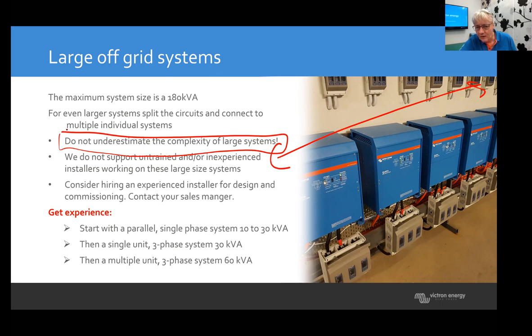Just try to calculate at 48 volts DC what the currents would be with a 180 kVA system. You need to know how to properly size cables, how to put bus bars in, what the problems with cables are. If you put really high current cables in a conduit, for instance, they heat up too much and the cable could melt just because they have a lot of current. Cables can even start repelling each other because of the magnetic forces around them from the current.